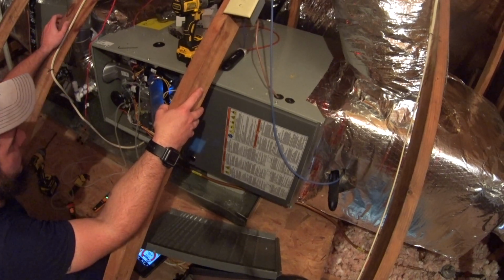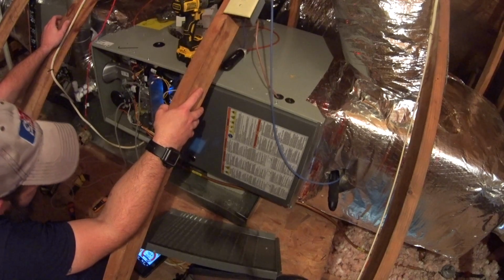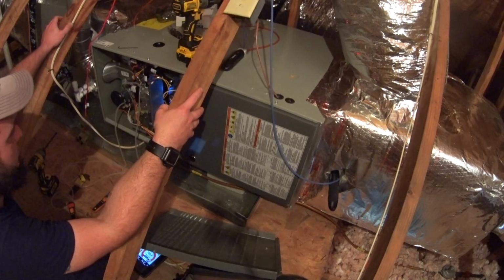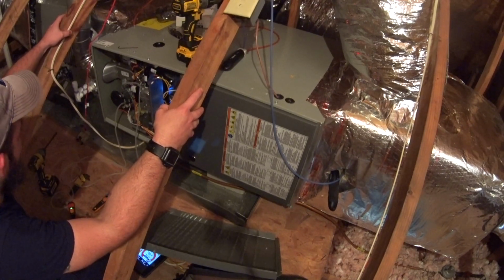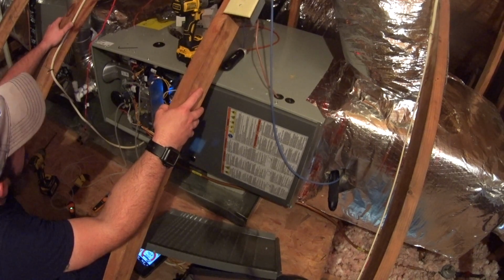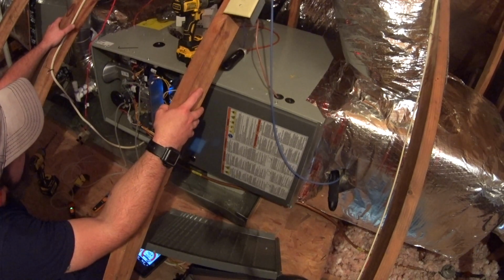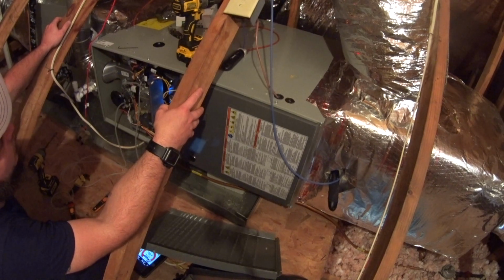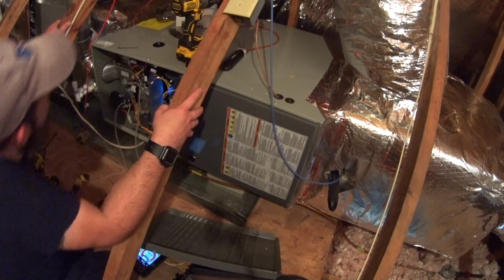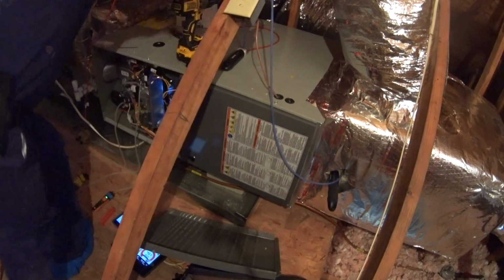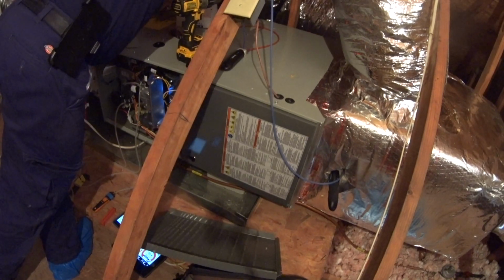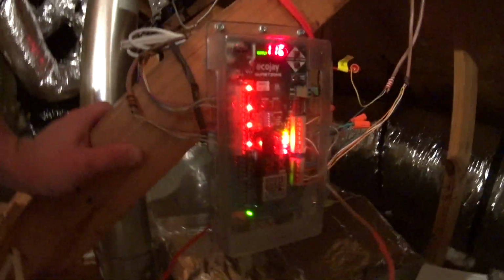It is climbing a little bit, and I haven't looked into the wiring yet, but I believe this is going to be a second stage timeout, as the wiring on the zone board does not show W2. The zone board is capable of two-stage. They are using one of my favorite zone boards, which is the EcoJay Smart Zone.